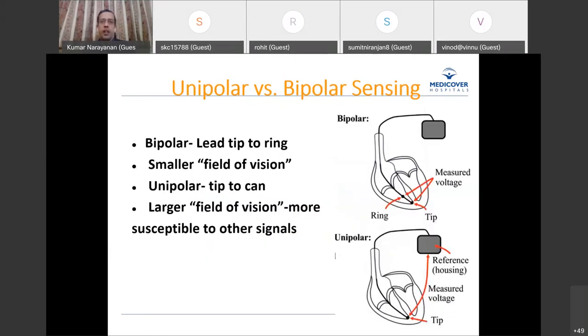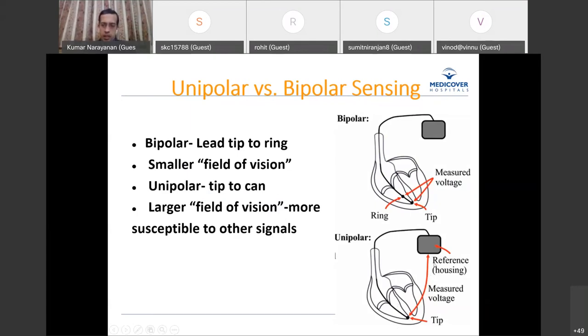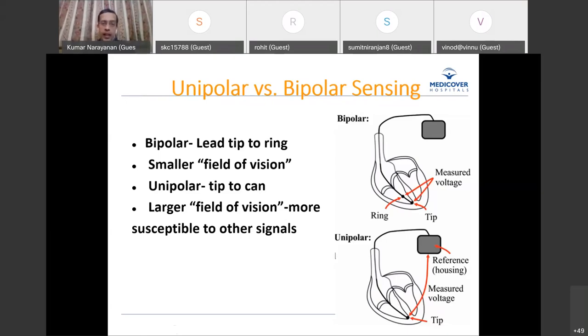Just like pacing, sensing can be unipolar or bipolar. Unipolar sensing is between the tip and the can — a large circuit with a large field of vision. Bipolar sensing is between tip and ring — a small field of vision or small antenna. Unipolar sensing is more susceptible to external signals because it traverses a large area. Bipolar sensing is less susceptible, and is the default setting, though unipolar sensing is available as a programmable option for troubleshooting.